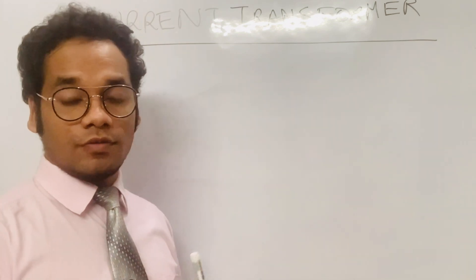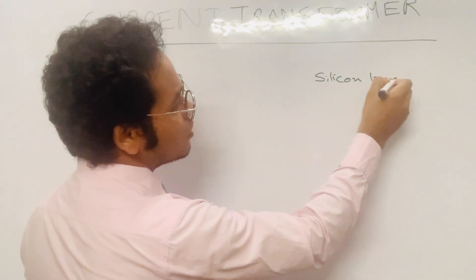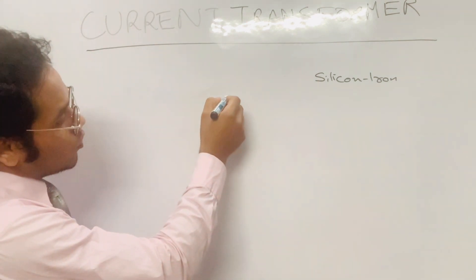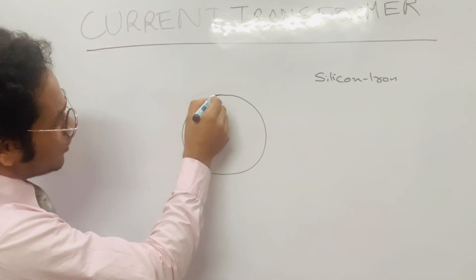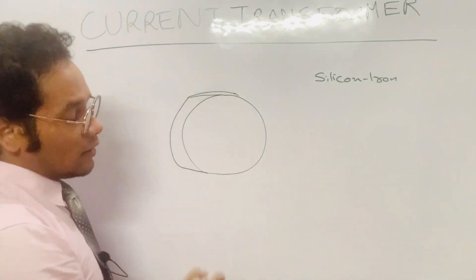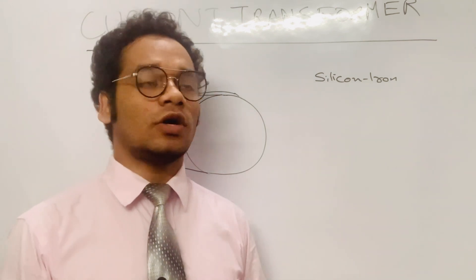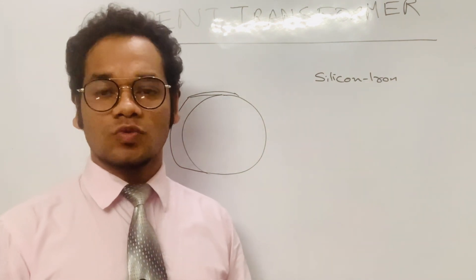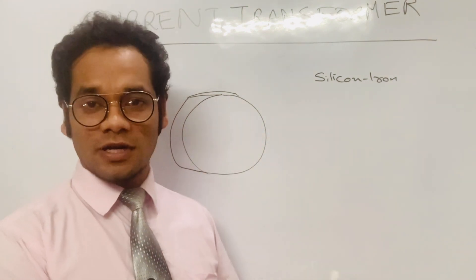In a current transformer we have a core which can be made of silicon iron. The current transformer core is basically in the form of a toroid. On this toroid a winding is wound, and that winding is the secondary winding. In a current transformer, it is only the secondary winding which is wound on the core — there is no primary winding on this core, and we'll get to know why a bit later.